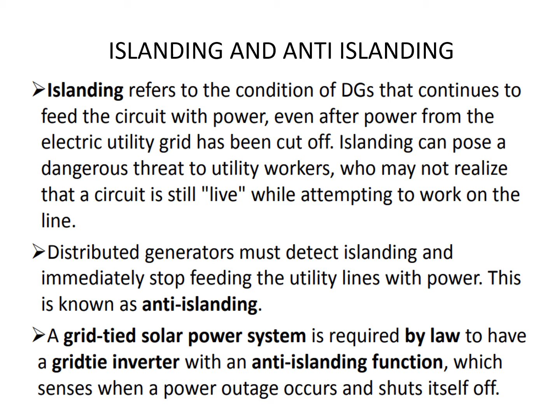So generally it is desirable to deactivate this anti-islanding protection scheme for the microsources, and the anti-islanding controls on their power electronic interfaces, unless the ratio of utility generation to microsource generation is too high. And this microgrid might be left with uncontrolled islands if these controls are not deactivated. So as the majority of these anti-islanding schemes cause very fast tripping, it is very essential to deactivate them instantly on detection of forming an isolated microgrid. And transmitting a blocking signal from the microgrid central controller is the most reliable way for deactivating the anti-islanding trip signal.